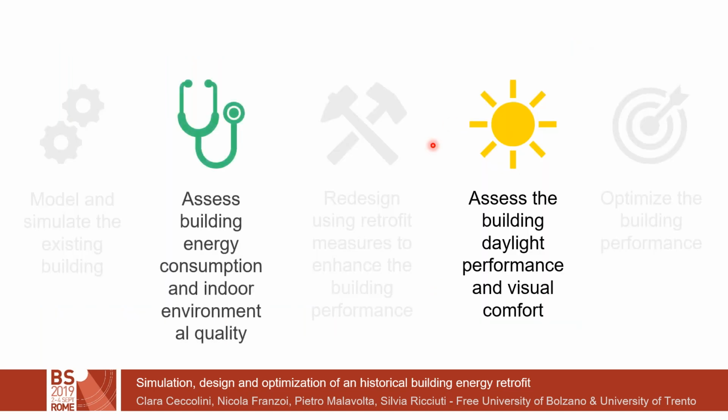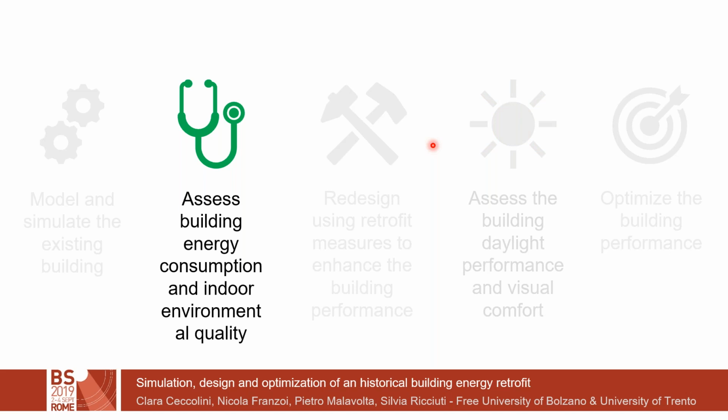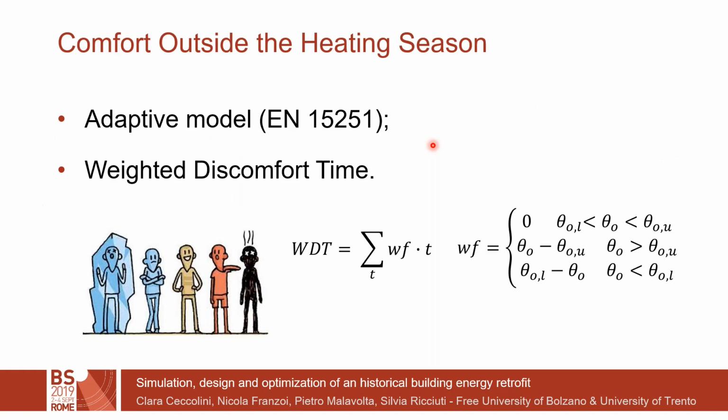Visual comfort is part of the indoor environmental quality, together with thermal comfort, which we evaluated adopting Fanger's and adaptive models as defined in the European standard 15251. The adaptive model is necessary to determine the comfort conditions outside the heating season.